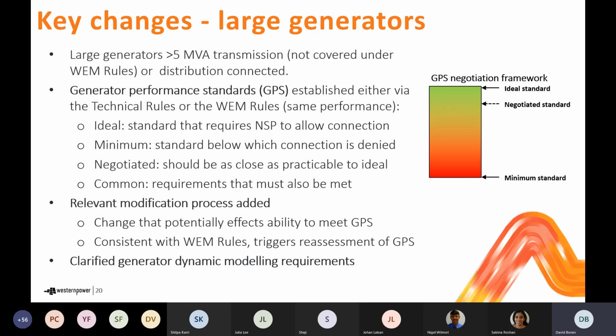So it's important that those modifications are assessed to identify whether there is any need to renegotiate any aspect of the generator performance standard, whether there's any need to redefine generator compliance arrangements, and in particular, often if it is a relevant modification, there will be a need for, once the modification's been made, some additional tests, commissioning tests and validation tests to confirm that after the relevant modification, the generator is meeting its generator performance standards.